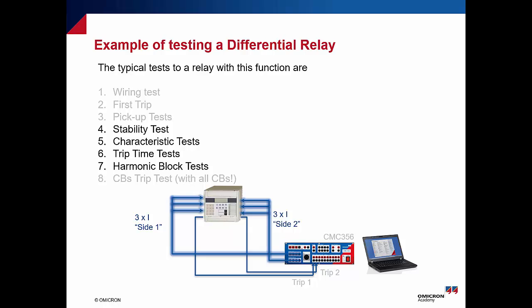Point number five is a characteristic test, the operating characteristic. We will talk about that one in detail. Number six is the trip time, to check the trip time of the relay. Number seven is a harmonics block test, and we will talk about that one. Only to highlight that we can check the second harmonics to avoid inrush current with the energization of the power transformer.